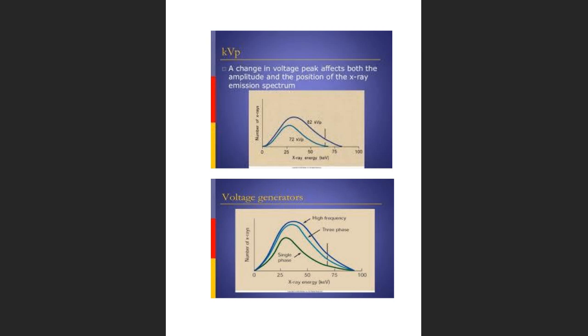Just trying to make sure that I have dealt with anything and everything that I can think of. Oh, and one of the things too, and this should make sense to you, is when we increase filtration of our beam, now I have an energy that is more compact, a harder beam.